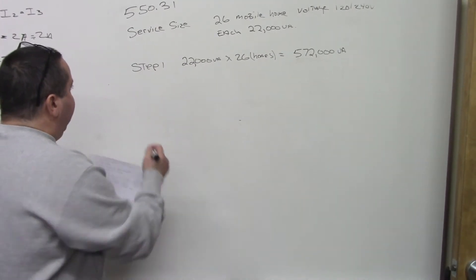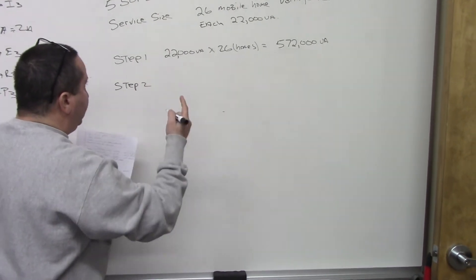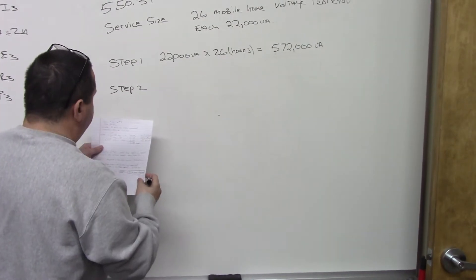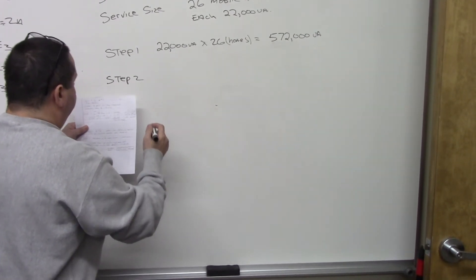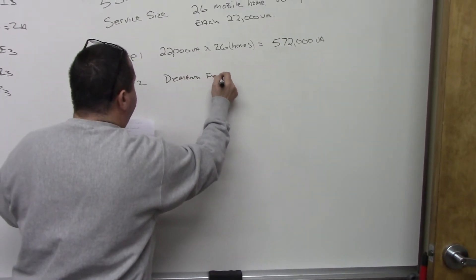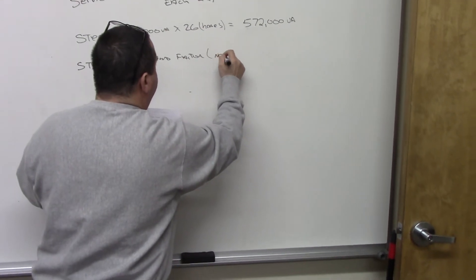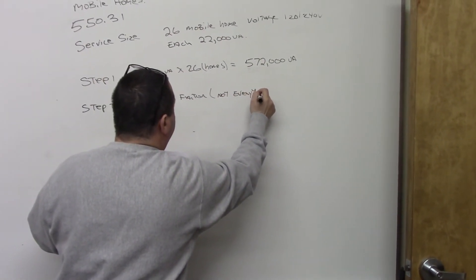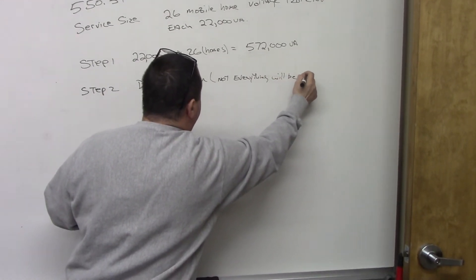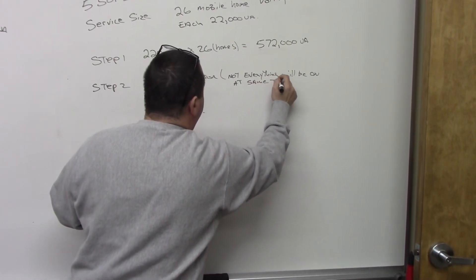So there's going to be a demand factor. And there's a table. So step two is a demand factor for these 22,000 volt amp mobile homes. The demand factor, meaning that not everything will be on at the same time.